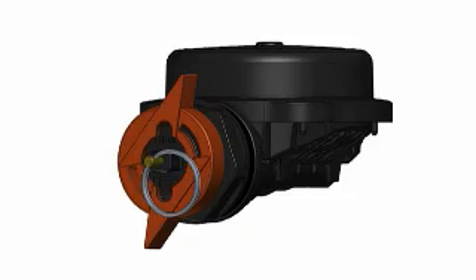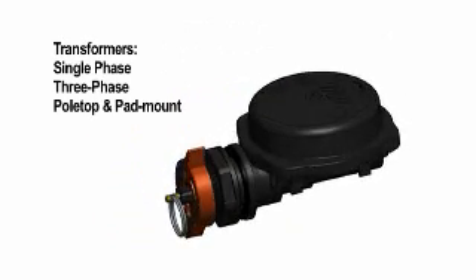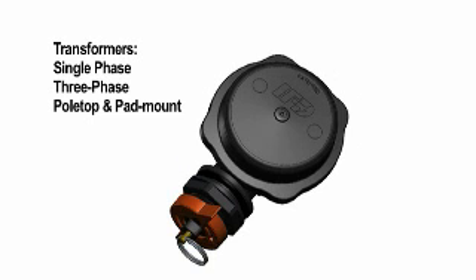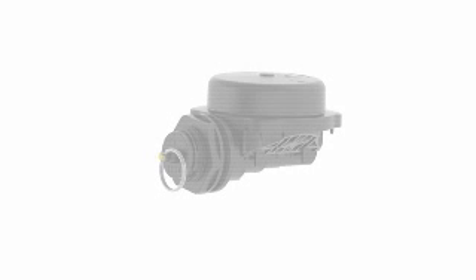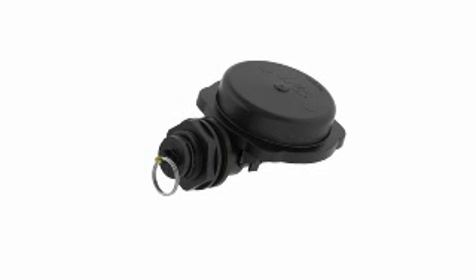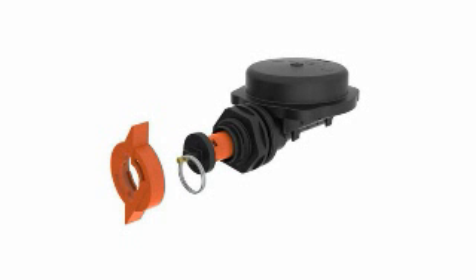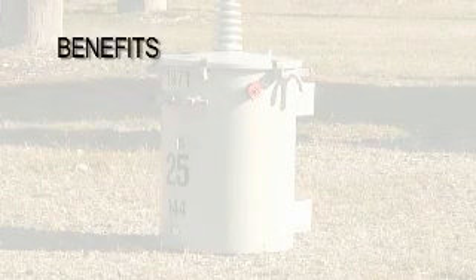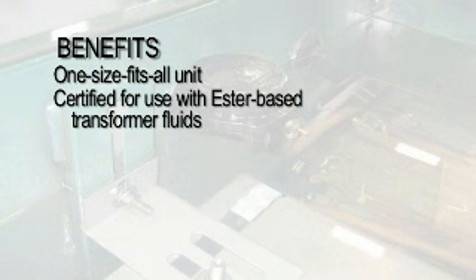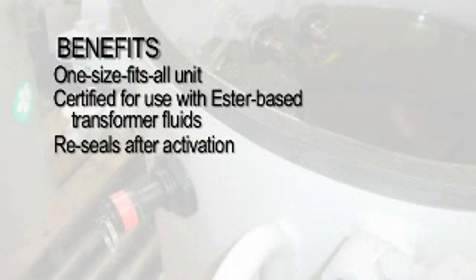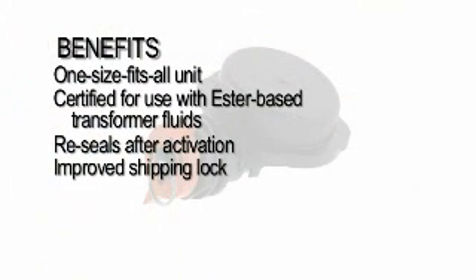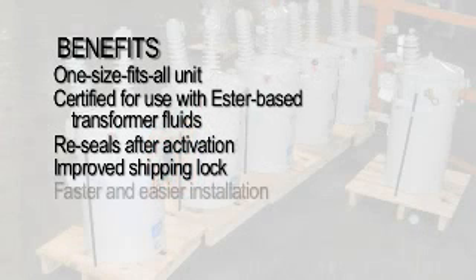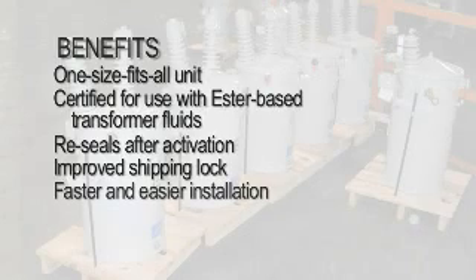The newest model of the IFD is a one-size-fits-all version that is applicable to single and three-phase pole-top and pad-mount transformers, as well as voltage regulators. It improves customer operations and handling and integrates more seamlessly with transformer manufacturing processes. The benefits of this new model include one-size-fits-all unit for single and three-phase pole-top and pad-mount transformers and voltage regulators, certified for use with ester-based transformer fluids, reseals after activation, preventing any oil spillage while removing a faulted transformer from service, improved shipping lock, easier to remove and install, faster and easier installation at transformer manufacturers.